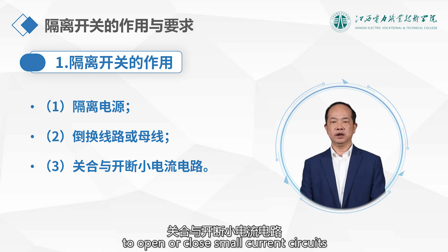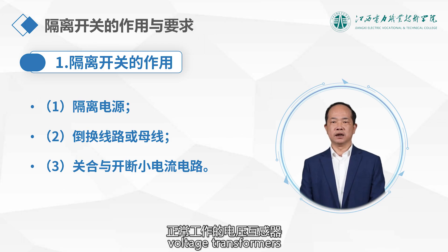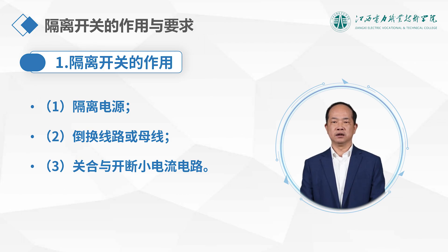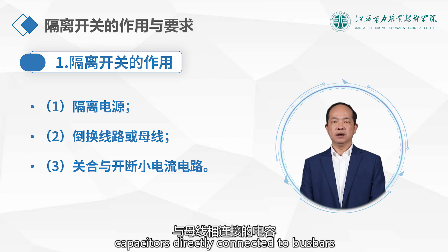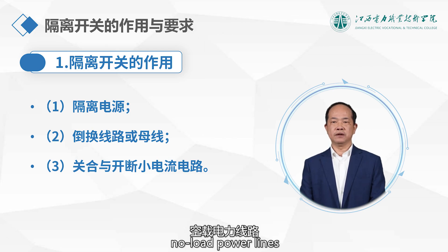Third, to open or close small current circuits. They can be used to open or close voltage transformers, surge arrestor circuits, bus bars and capacitors directly connected to bus bars with capacitance currents no more than 5A, and no-load power lines with magnetizing current no more than 2A, and no-load transformers, etc.